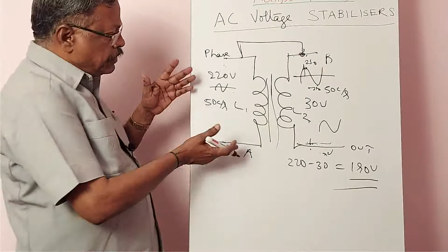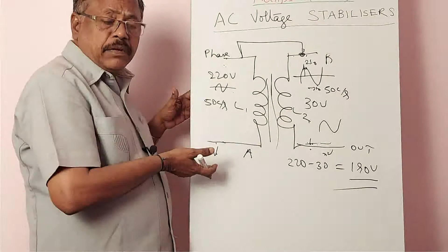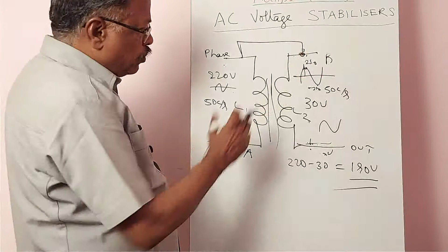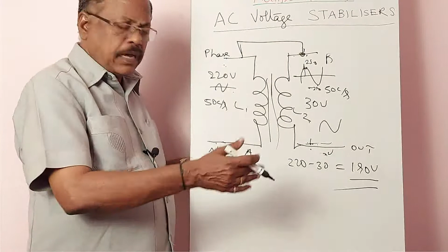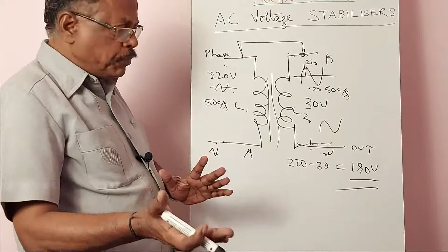So by properly manipulating the connection of the terminals of the primary with the secondary terminal, even though the incoming voltage is 220 volt, with a transformer like this I am able to have either 250 volt or 190 volt. In one type of connection I can have 250 volt, 220 plus 30. In another type of connection I can have 220 minus 30, so 190 volts. So from this itself we can understand that a stabilizer can be made by having a transformer alone, which has primary 220 and secondary 30 volt.